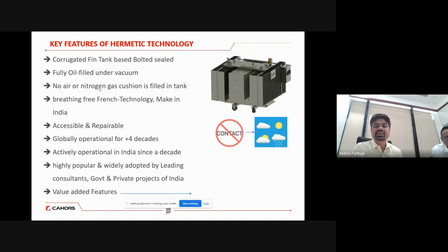And in case of anything, by means of low loading factor or extreme atmospheric condition or no continuity of service of the transformer, because the manufacturer may not be aware in what condition the transformer is used, in such cases the periodic sampling helps us decide the action plan for proportional maintenance if it is required. If everything goes well, then things can be taken for the next 5 years in the same manner, and things can go on as per the similar regular checkup.